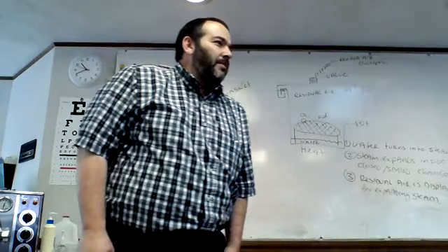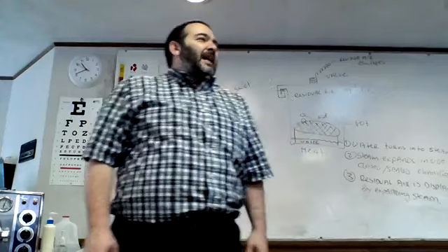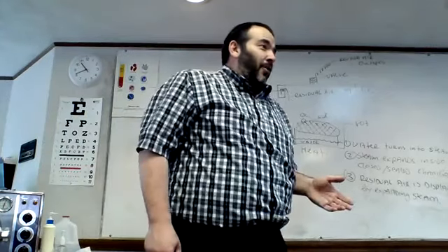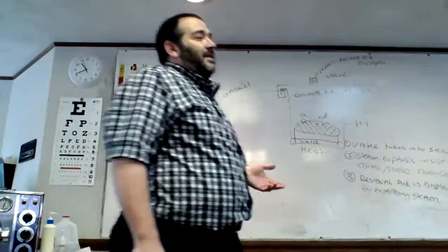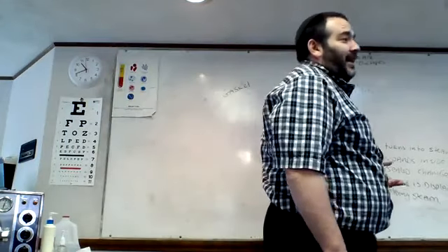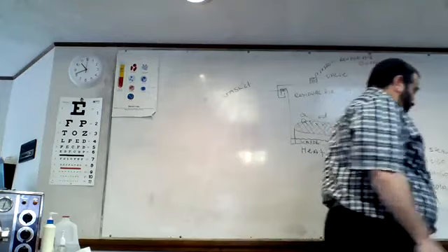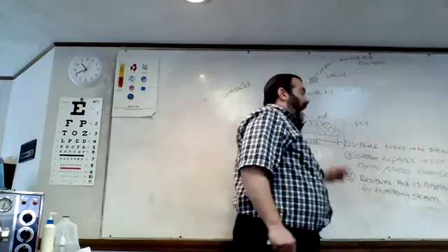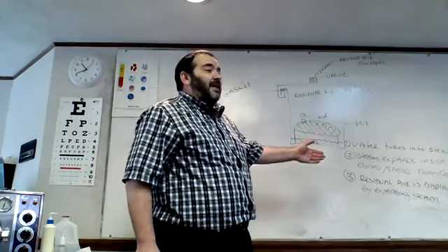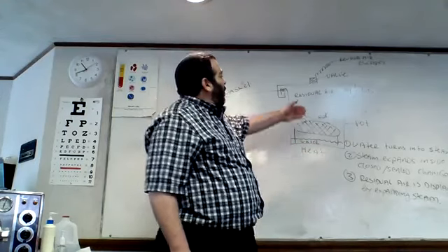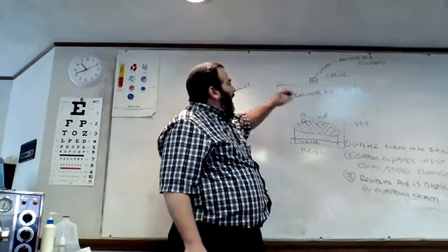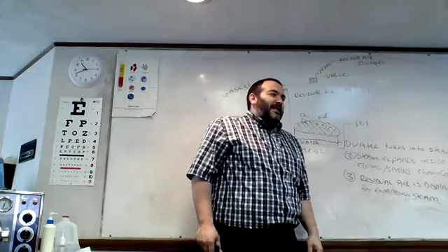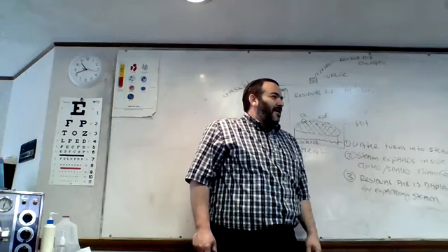So far, so good? So in essence, there is no air during sterilization. It's very important because air is a great insulator for heat and for cold. So we want to get rid of the air. And how do we get rid of the air? By expanding the steam inside the chamber. The question becomes then, how does this valve differentiate between steam and air?